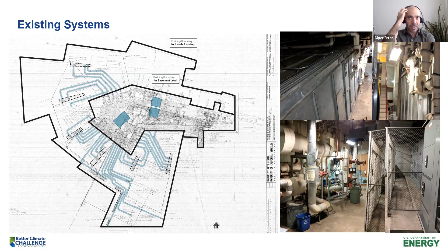As I mentioned before, the building posed challenges since we couldn't change the facade openings or any other openings between the concrete walls, which limited the air capacity that could be brought into the building. The existing building system included a total air intake capacity of 60,000 CFM from outside, so we were limited to this capacity since we couldn't add additional louvers or risers to bring in more air.